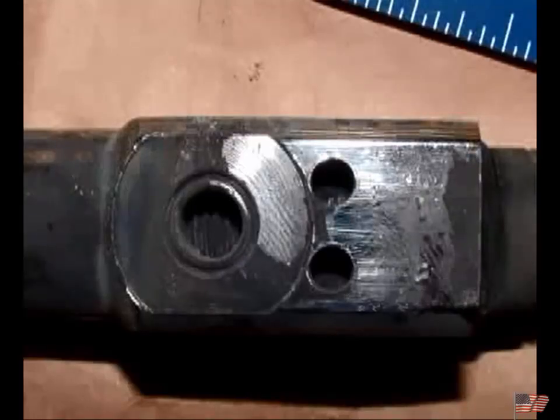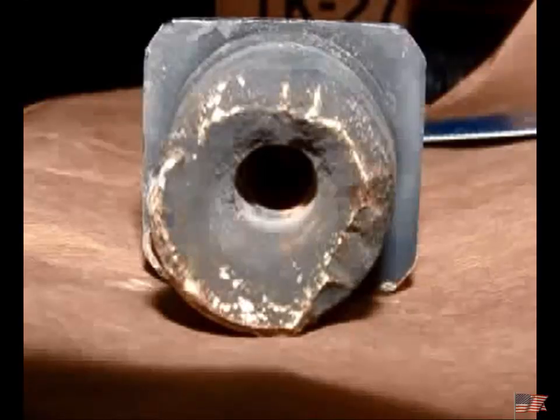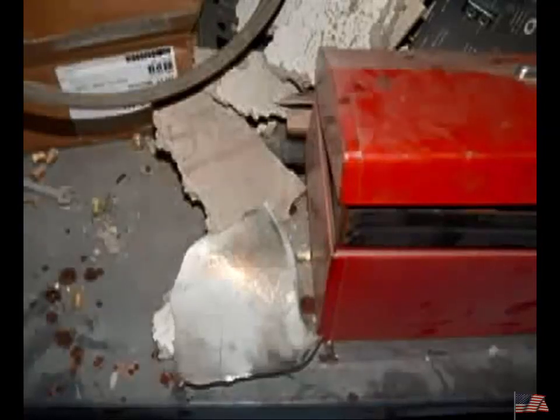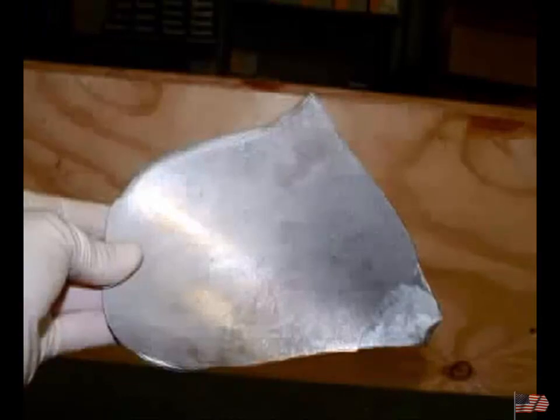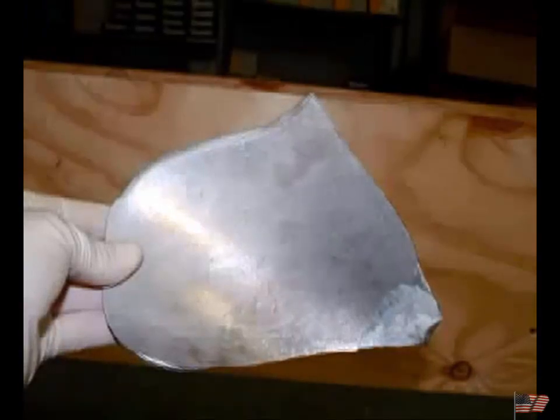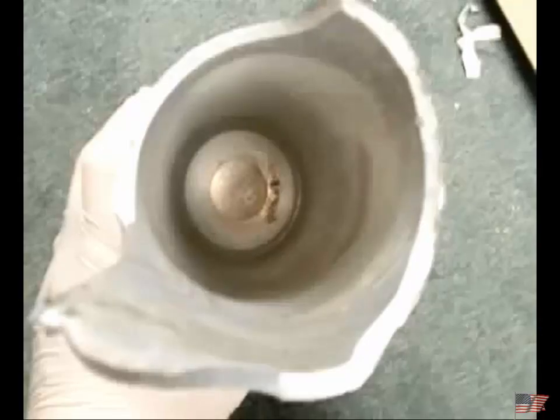You can see, if you look a little closer, that the force of the explosion was so hot that it melted the cylinder valve on the inside of the tank. This is a piece of shrapnel from the top of the cylinder. This is another piece of shrapnel from the top of the cylinder. You can see it's pretty much flattened. Remember, this is an E-cylinder, showing how sharp the edges are. This again is the cylinder itself, looking down inside the cylinder.